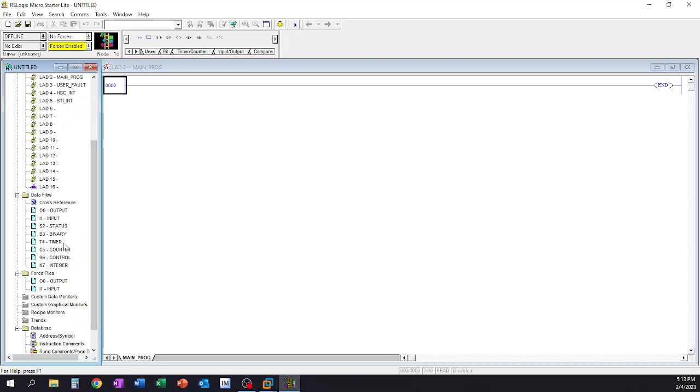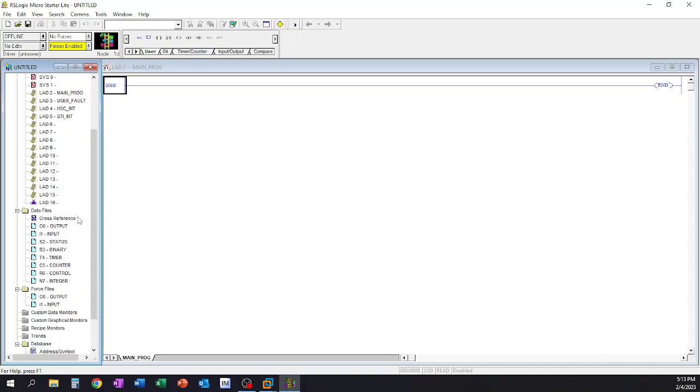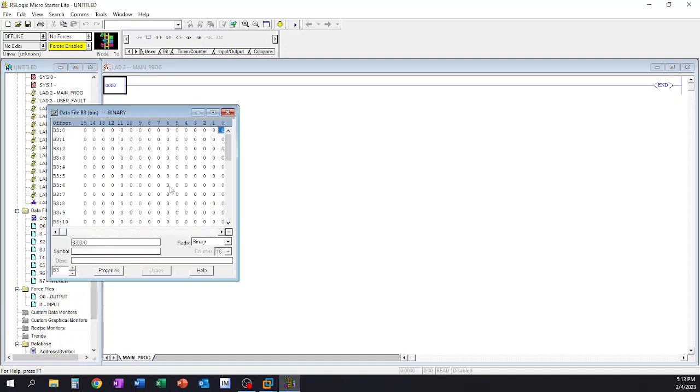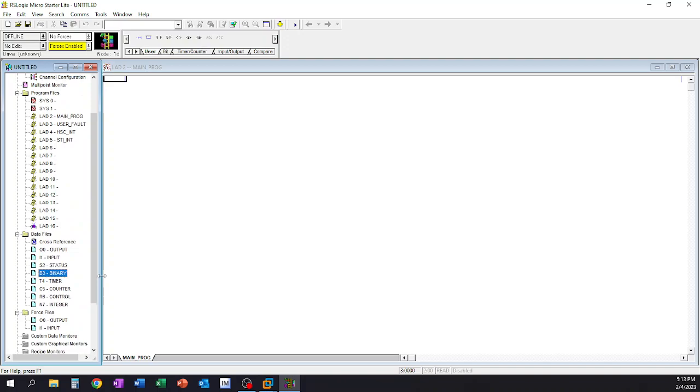One of the things that really set 500 apart from 5000, either RSLogix 5000 or Studio 5000 is the data files. So the data files were automatically created for us depending on what our information was that we created in our IO configuration. So again, if you had a chassis, it went ahead and created all of that stuff automatically for you. You couldn't deviate from what the data files created for us. You could add, you could continue to add and grow up. So like for instance, if we open up our binary folder, our binary is going to stop after 31. And I believe that's a standard probably for the MicroLogix. But when we get into like the 505 processor again, we could continue adding on beyond that and have more binary bits. In general, and generally speaking, our data files and everything are already set based on the inputs and outputs that we have set in the IO configuration.